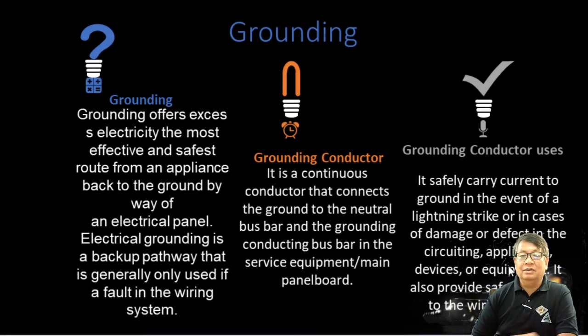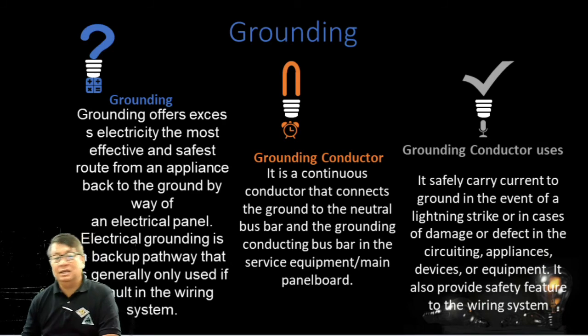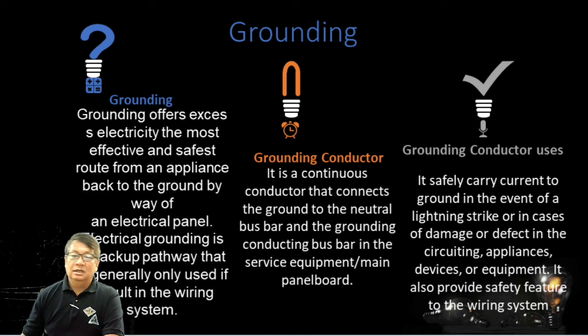So, when we say grounding, this offers excess electricity the most effective and safest route from an appliance back to the ground by way of the electrical panel. So that is the grounding system. Electrical grounding is a backup pathway that is generally only used in the event of a fault in the wiring. Okay, so we have this. So grounding conductor is a continuous conductor that connects the ground to the neutral bus bar and the grounding conductor bus bar in the service equipment.